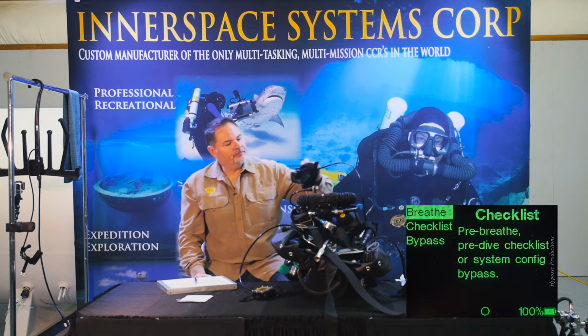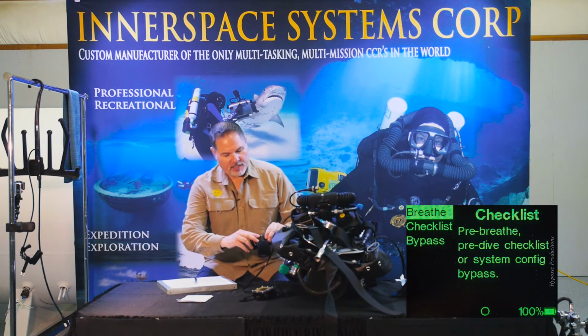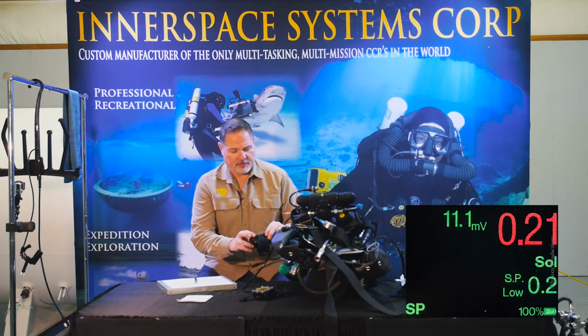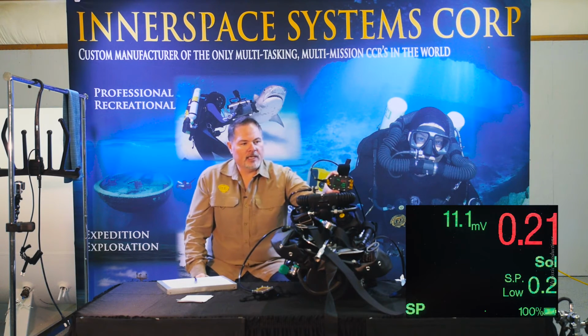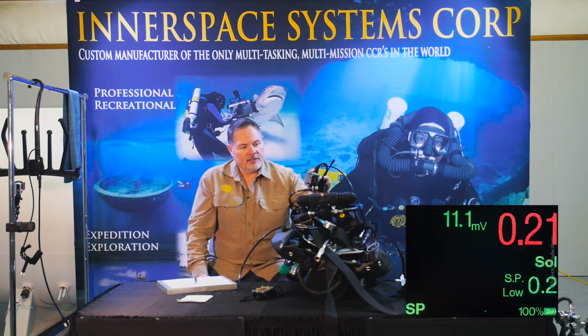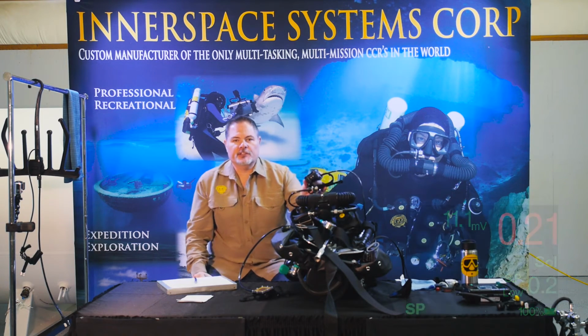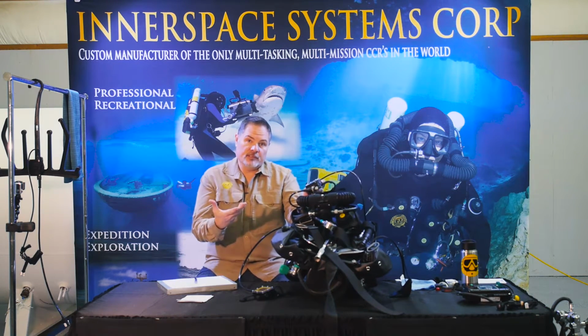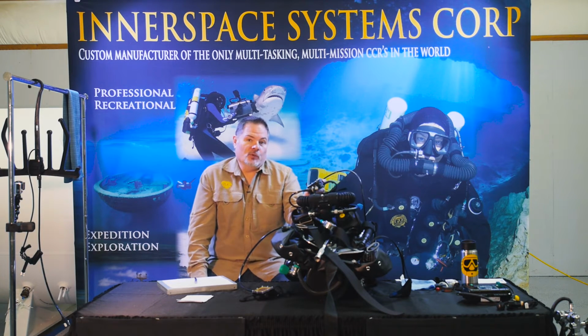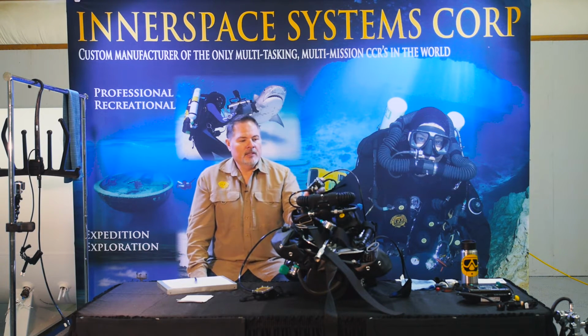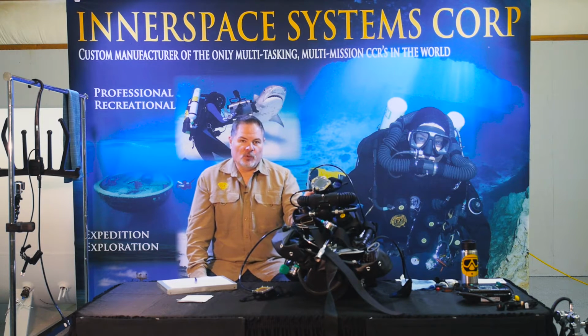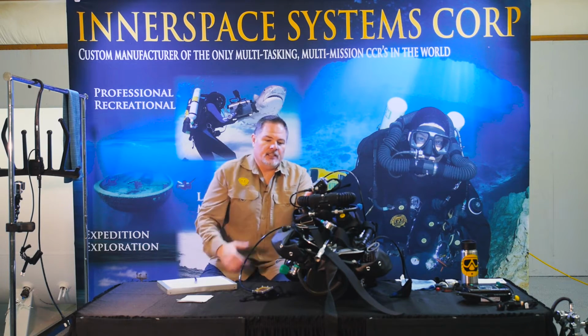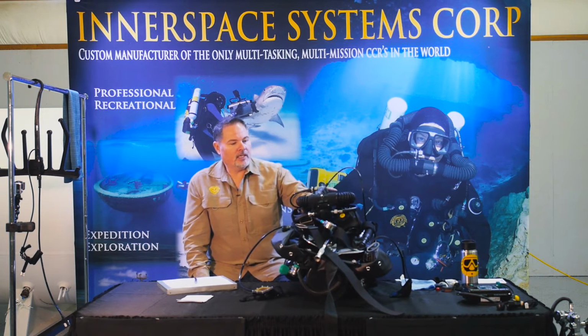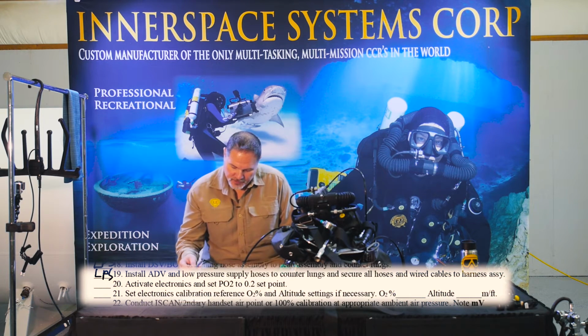Okay, good to go. So what I'm going to do is go down to bypass on the handset itself, and right now it's set for 0.2 mode. That means the solenoid is turned off at 1 atmosphere here at sea level. You're breathing roughly 20.9% or 0.209. So the default for the handset is 0.2. Unless you're up at altitude, you should not hear the solenoid engage. All right, so the system is locked into 0.2 and activated.